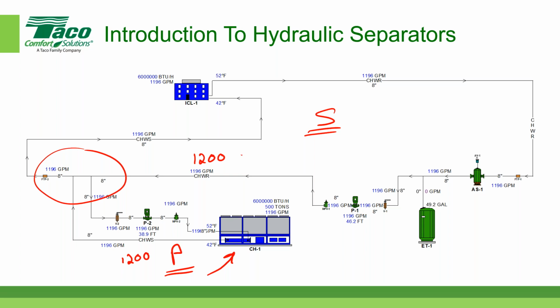And again, if we allow the secondary circuit to drop, let me just erase that one little thing there. Let's erase this here. If we allow the secondary circuit to diminish, let's say it drops down, and again, let's make that 600 gallons per minute, then what happens is that across this bridge right here, that would be 600 gallons per minute. So let's put that 600 up there. So it's just a slightly different way of looking at the same problem with a slightly different piping configuration. And this might be a little bit easier, not easier, but a little bit more familiar to what most people would see for a piping system.